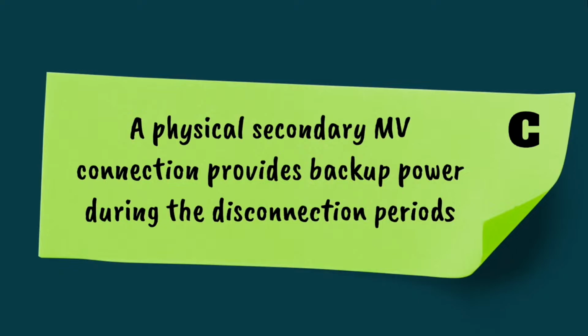A suggestion is to consider having a secondary grid connection, typically connected to the medium voltage network, which would not be used throughout a typical day of the year, but which would be there for these emergency shutdowns on the TSO side. In that case, having this connection would power medium voltage operations of your wind farm throughout this shutdown period, so it would effectively be a backup.